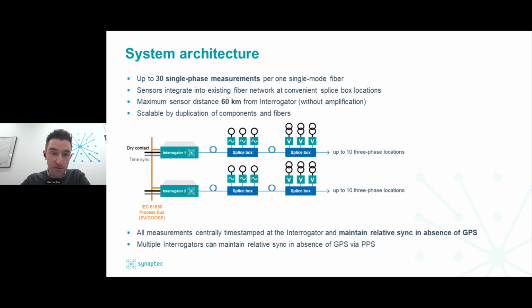And without using any additional amplification, the maximum sensor distance is about 60 kilometers or around 40 miles from that central interrogator. And with amplification, we can stretch that further. Each interrogator can output IEC 61850 sampled values directly to the process bus, and it can accept standard time synchronization formats like PTP and PPS. And it can also output in traditional dry contact format for traditional systems.